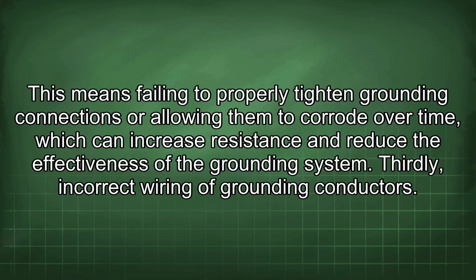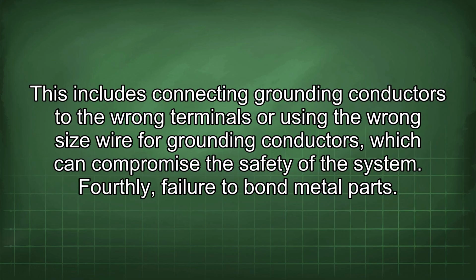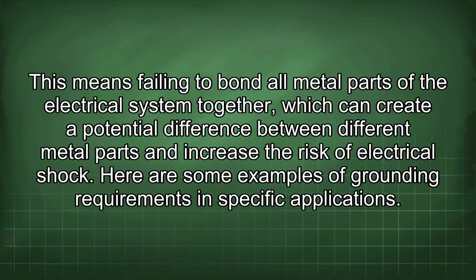Thirdly, incorrect wiring of grounding conductors. This includes connecting grounding conductors to the wrong terminals or using the wrong size wire for grounding conductors, which can compromise the safety of the system. Fourthly, failure to bond metal parts. This means failing to bond all metal parts of the electrical system together, which can create a potential difference between different metal parts and increase the risk of electrical shock.